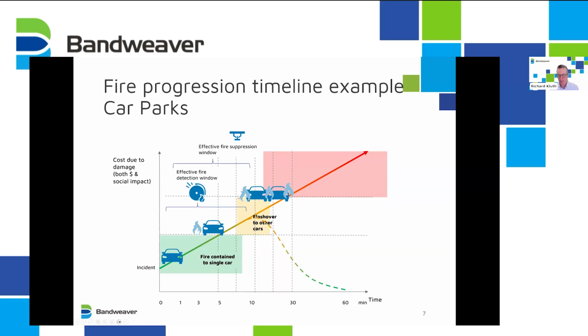Once you start to get flashover into other cars, you then enter this yellow amber period where, unless you catch it very early on, you're past the stage where local suppression can be effective, and typically the fire department will get involved, but by this stage there's already significant risk to infrastructure. So in each of the examples we'll use this graph as a framework for looking at each of the incidents. So starting with King's Dock car park in 2017.